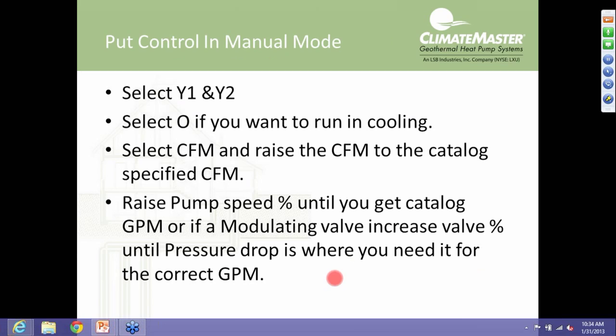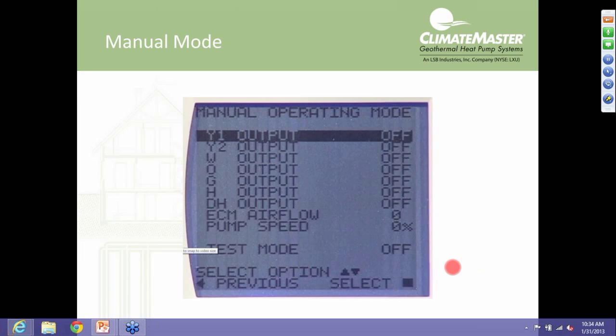Next bullet up is our CFM. Again, we'll go to our CFM and raise our CFM to what our specifications are for that heat pump to commission it. And then if we want to run it in the cooling mode, we're going to energize O next, and then Y1 and Y2. We're going to get it running for 10 or 15 minutes, and then we'll take our entering water and our leaving water temperatures off of the service tool or the thermostat. Here's just a screenshot of the manual operating screen, again, what you'd actually see. Again, and then we would make those changes as we've talked.